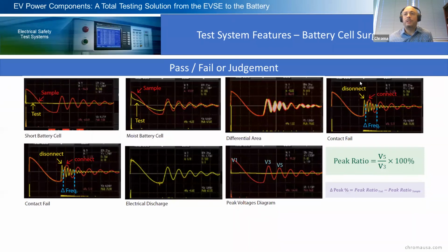On the first one, we could see the difference between a shorted battery cell and a moist battery cell, and that's for the area. Then, moving to the right, the differential area. Then we have a flutter, where you lose contact during the test and it gives you a little flutter, which is the total value of the waveform that is calculated. Then we have a Laplacian type test, which calculates the second derivative of the differential equation. You can check the occurrence of a small discharge. You can also detect rapid changes in the test waveform caused by a small discharge during a surge test.